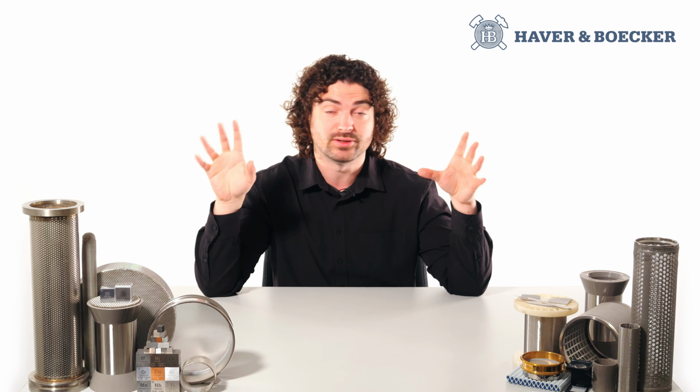Maintaining steady fluid velocity and sharp, clean peaks is a constant challenge in production laboratories. When a proven method displays wide peaks, a drifting baseline, or high back pressure, operators often blame chemical or solvent quality.